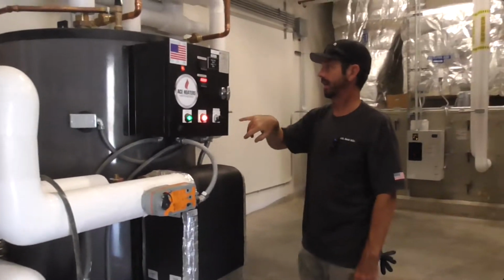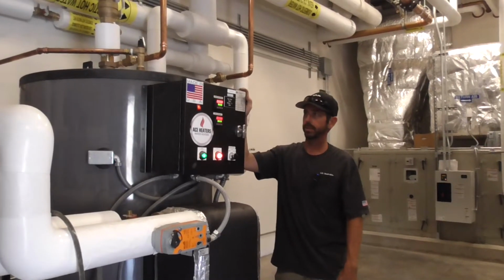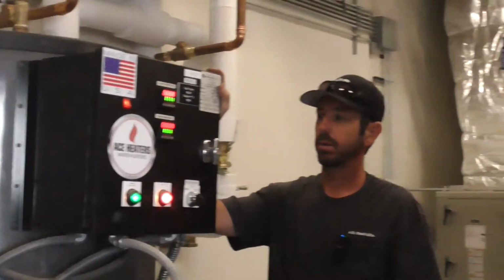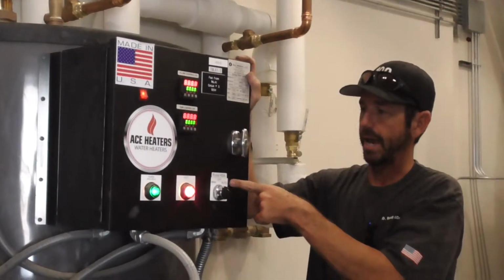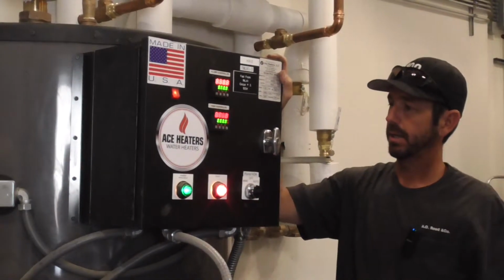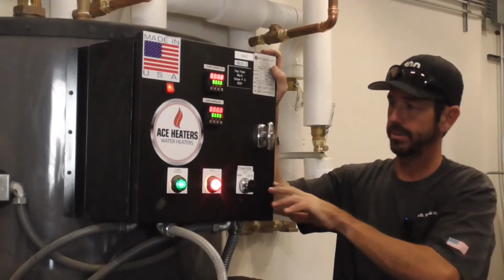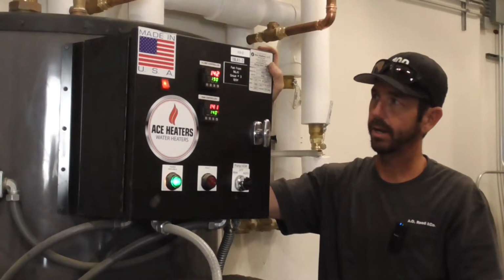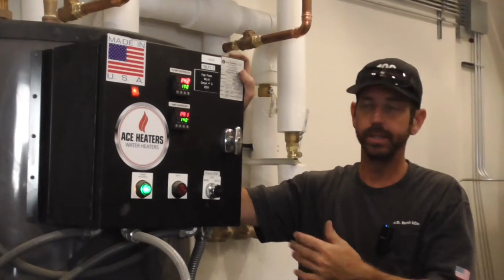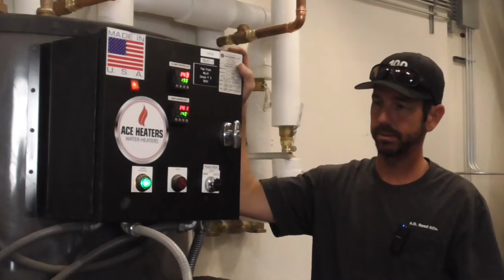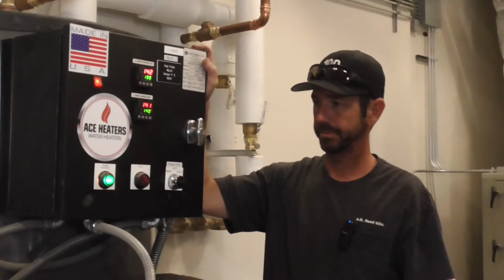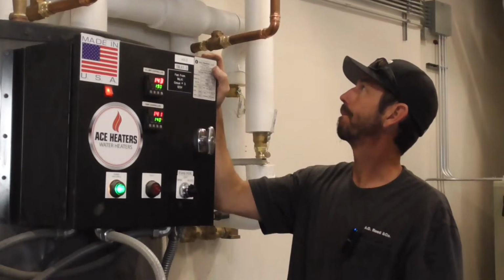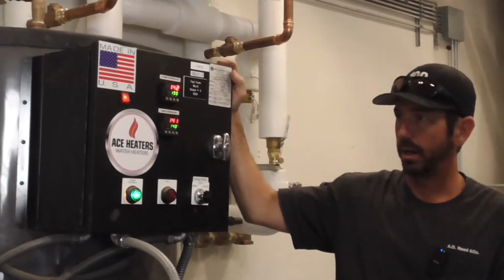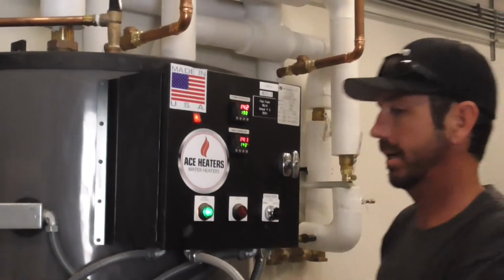Now we turn it on, we get all of our lights, we're going to boot up the controller. Once it's booted up and it's turned on, you can have this in auto before that. So right now the controller's still booting, so it's not turning off the pump quite yet. We just heard the contactor pull in, so now it's calling for the heat. Again, there's redundant units here.